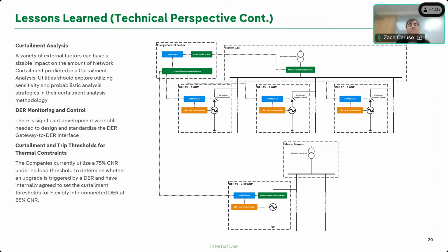And so we had to work through that in depth in order to get these sites up and running and operating reliably, getting those signals and then actually curtailing to the level we asked, and not curtailing like half the inverters. And then we go, well, you didn't curtail all the way, and so we start tripping them offline because they're not complying with our set points.